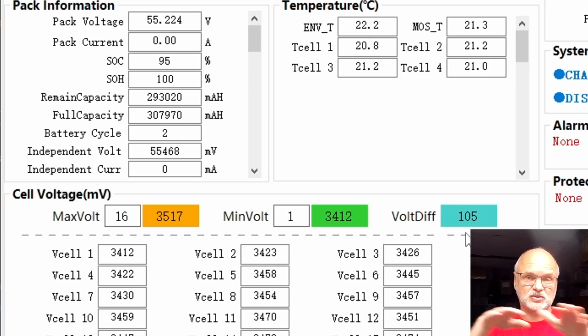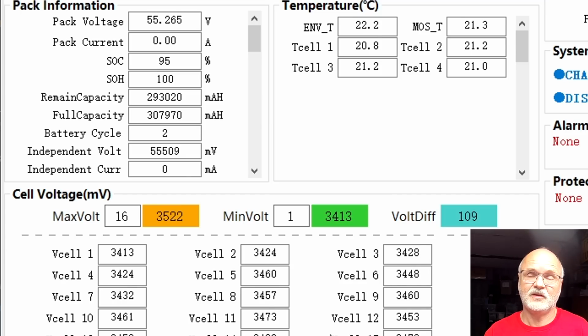I usually would stop charging here and keep the voltage constant, let the battery absorb, and let the balancer do its work. At this voltage we don't even have a cell high voltage alarm, nor a protection, nothing. It's just 100 millivolt, it will balance itself out automatically. And 55.2 is where I would turn on the balancer, not before that.